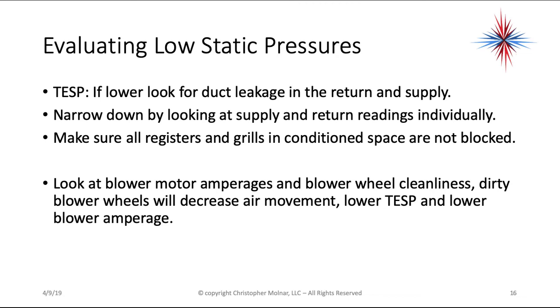To evaluate a low static pressure — if static pressure is lower than it should be — look for duct leakage in the supply and return ducts, and narrow it down by looking at supply and return readings individually. Make sure all registers and grills in the conditioned spaces are not blocked. Also look at blower motor amperages and blower wheel cleanliness. Dirty blower wheels will decrease air movement, lower the total external static pressure, and lower the blower amperage, because the blower has to work less when it cannot pull air.